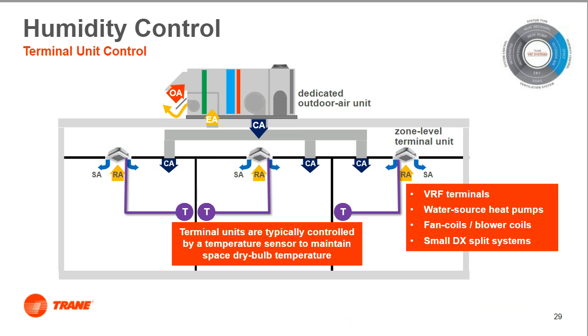A proper HVAC system must take into consideration the design of the dedicated outdoor air system unit, as well as the zone terminal systems, in order to ensure that proper space temp and humidity is being addressed. With a proper control solution and an adequately sized ventilation system, your comfort cooling system will have the ability to turn even the most humid environment into a pleasing space for all tenants.